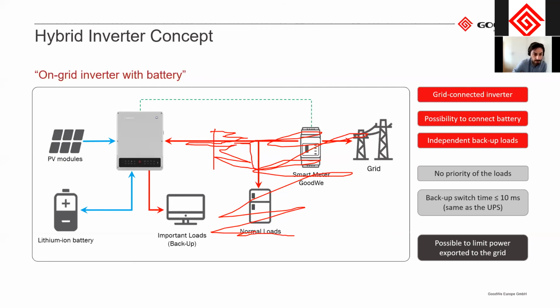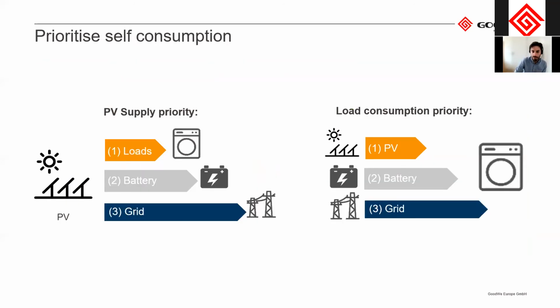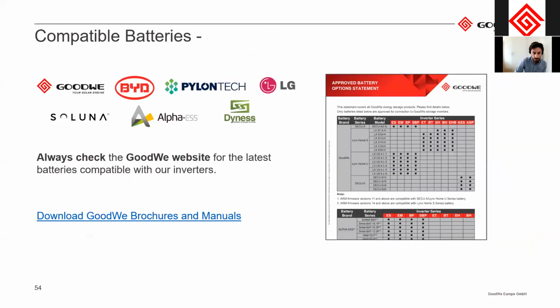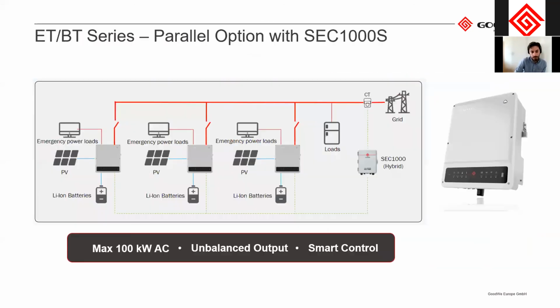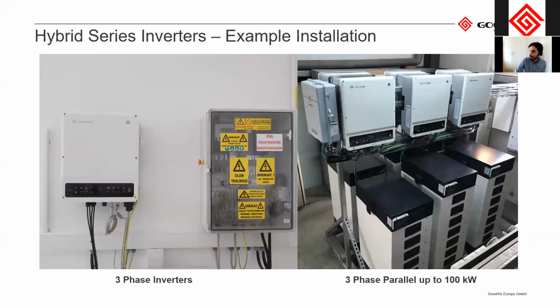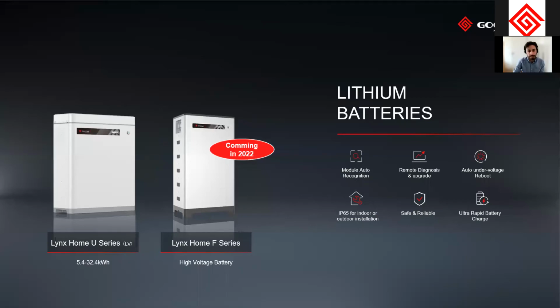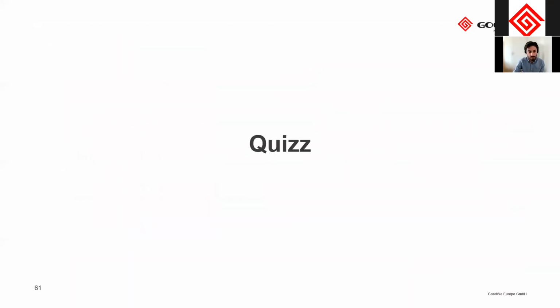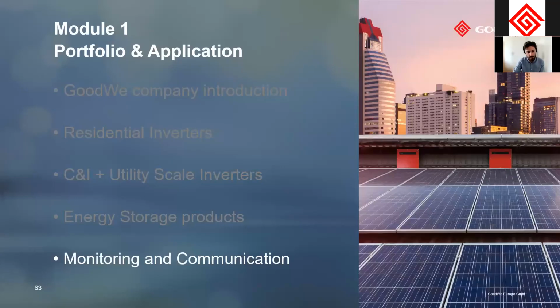And therefore, it needs to disconnect from the grid, but this one makes it possible that you can separate some loads in your household and then connect, for example, your lamps, your TV, some Wi-Fi, some necessary loads that you can use. What's important is that you don't connect too many loads to the backup output. So if you have a stove, oven, maybe AC or heat pump, then this is not recommended to connect because they usually draw too much power for the backup output.